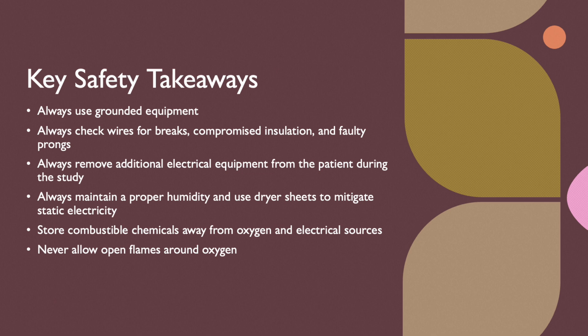All right. What to remember from these slides? Use grounded equipment and make sure that all of the grounding equipment is grounded. Always check the wires for breaks, compromised insulation, and faulty prongs. Always remove additional electrical equipment from the patient during the study, like a watch or headphones. Always maintain a proper humidity and use dryer sheets to mitigate static electricity. Store combustible chemicals away from oxygen and electrical sources, and never allow open flames around oxygen. Fairly simple stuff.